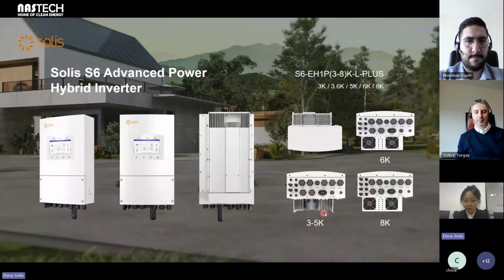The 3 to 5 kilowatt and the 6 kilowatt have 2 MPPTs and 2 input strings, but the 8 kilowatt has 2 MPPTs and 4 input strings.